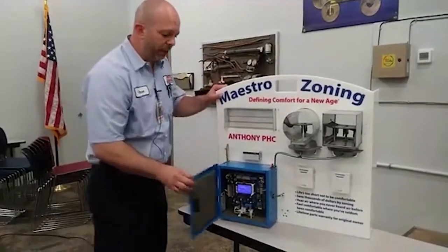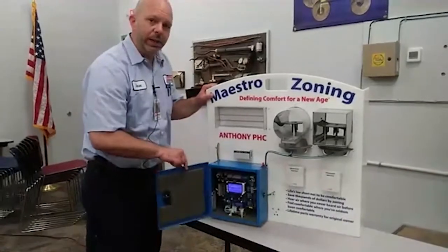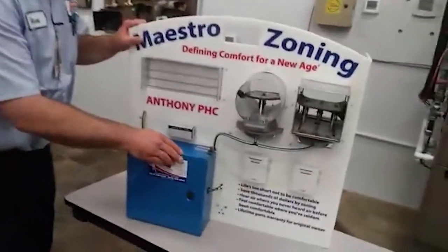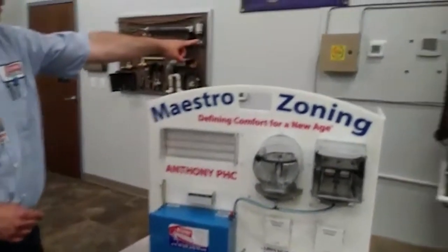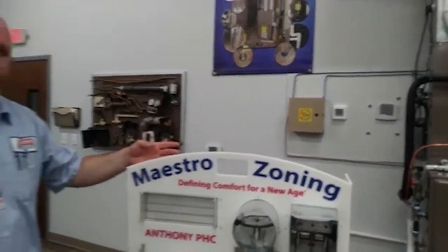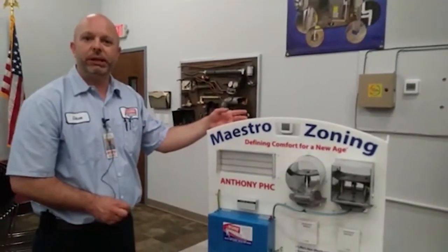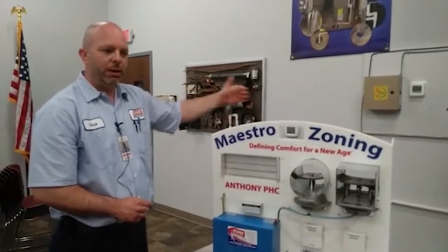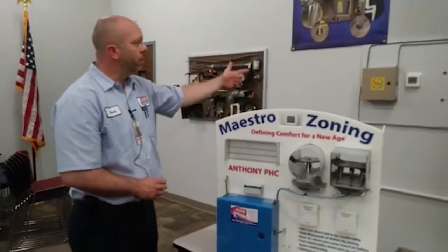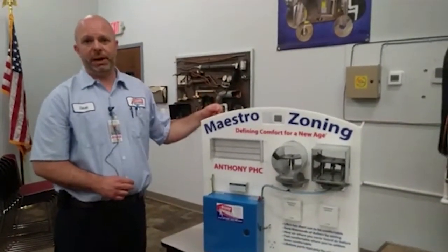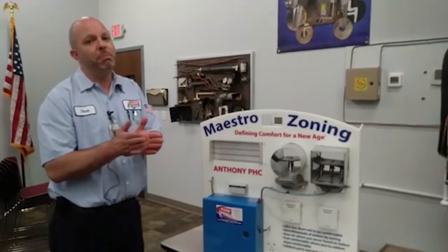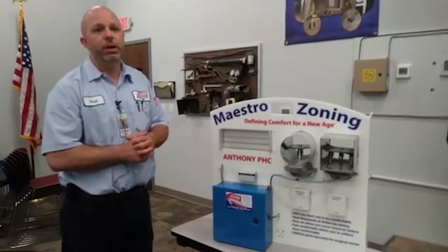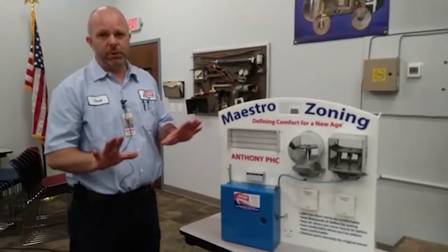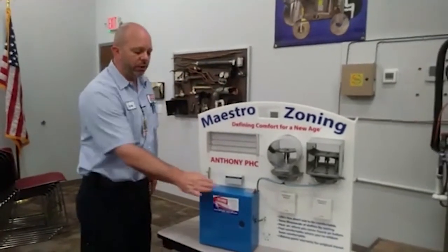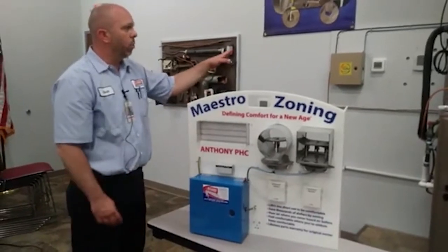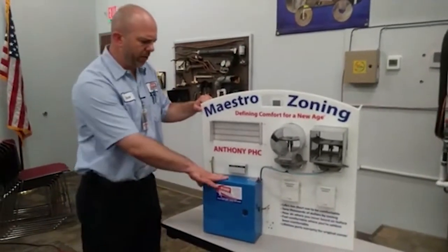Well, this is our little demo right here, and you maybe can hear some of that noise on this broadcast. What we do when we install it - we've got one back here on the wall, and when we put them in a basement, it's attached typically to a cement foundation wall. So we're going to put an isolation barrier with some insulation, then put plywood over the top of that, and then mount that zoning panel. What that's going to do is take away the noise and the vibration, so you won't be able to hear that upstairs. And if you have a utility room that is closed in, you wouldn't be able to hear it either. So just in case someone noticed the noise, they are much more quiet when they're mounted up on that wall. It's kind of vibrated through this table a little bit.